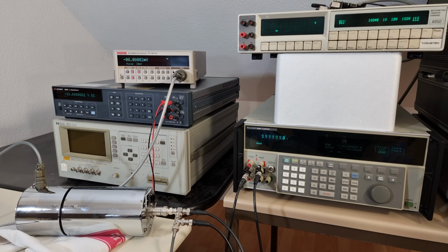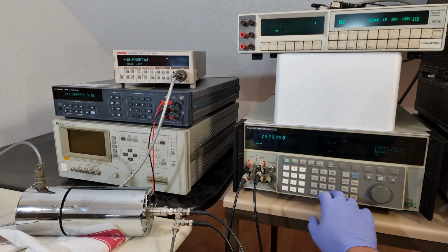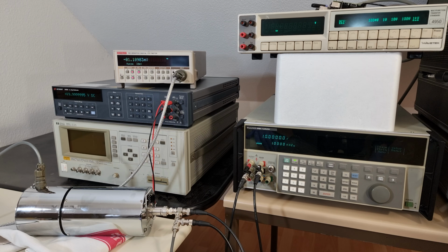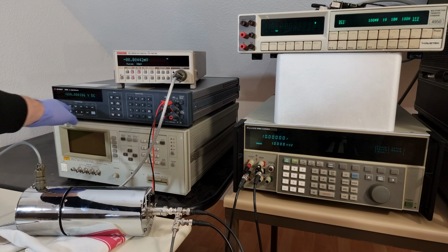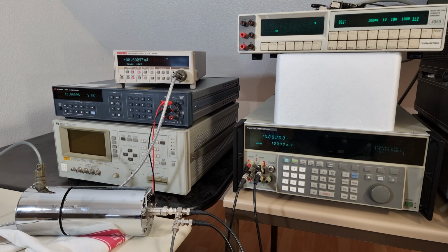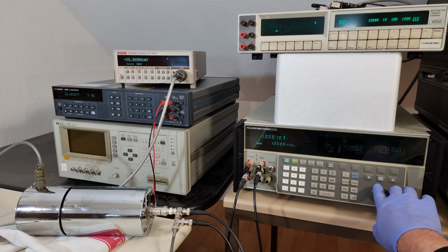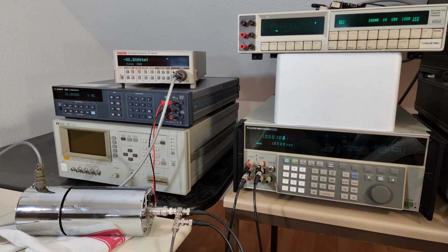And what do you know, let's do just that. 1 kHz 10 volt RMS coming right up. On the nanovolt meter we can see a short drop in the converter temperature while the calibrator is rearranging itself internally. Let's see what 3458A's electronic RMS sensor has to say about this. Fluke 5700 should be pretty good at this, because if you remember, it uses thermal RMS sensing techniques internally too. But yeah, after 10 minutes of settling time there does appear to be a 108 ppm difference between Fluke's AC and DC ranges, and an even more severe discrepancy in 3458A. Although that is easily within spec because I'm in the power on default analog computer measurement technique. That meter can do much better, I just forgot to switch to synchronous mode, sorry.